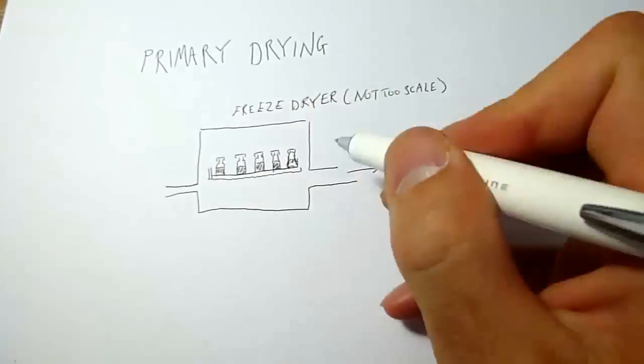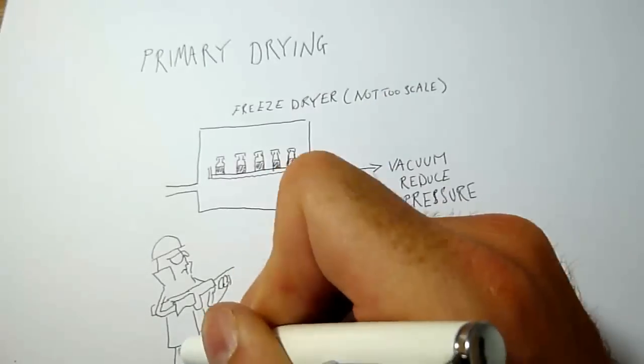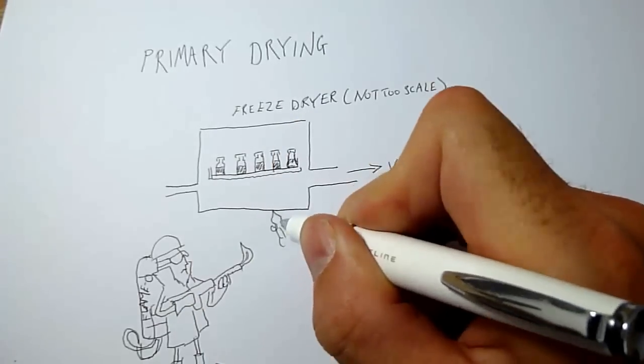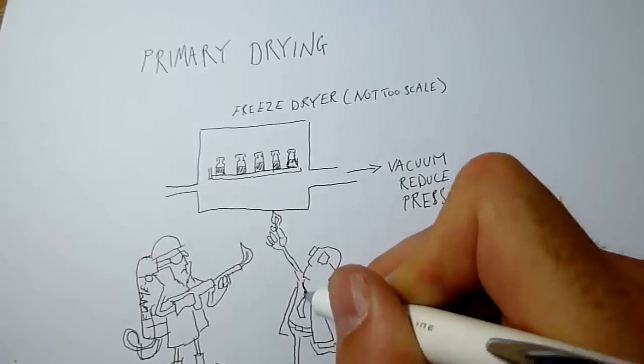Primary drying: During this step, the pressure in the drying chamber is lowered and a very small amount of heat is applied to the sample. This part of the process can take days in an industrial drying cycle, as if too much heat is applied, the structure may be altered or destroyed. If drying time can be reduced, there is another opportunity to reduce costs.